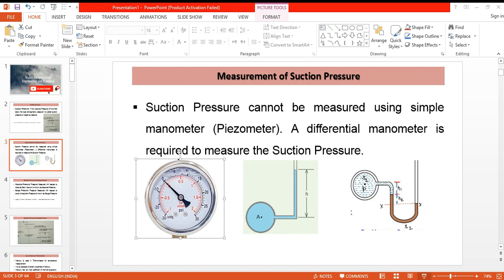Similarly, a simple piezometer or simple manometer having a single limb will not be able to measure the negative pressure because here we can see that only positive pressures can be measured. There is no provision for measuring negative pressure. So a differential manometer or a U-tube manometer will be required to measure the suction pressure.